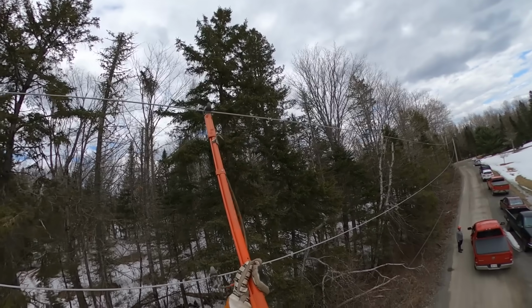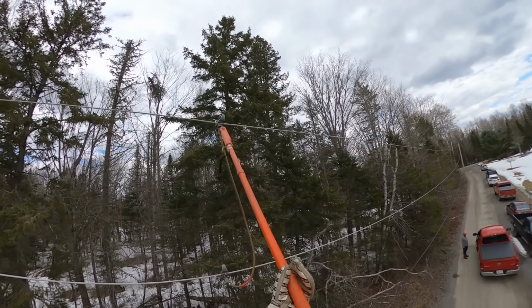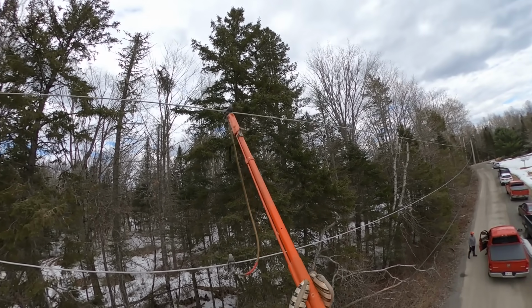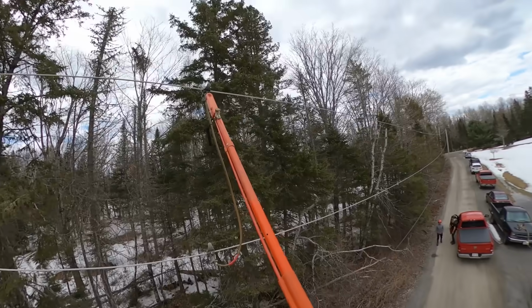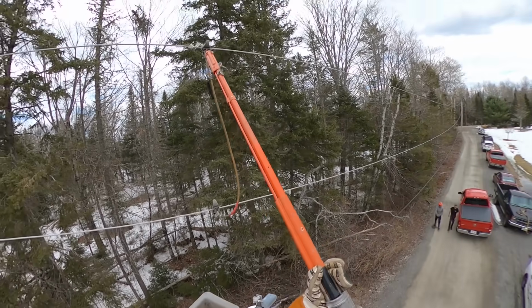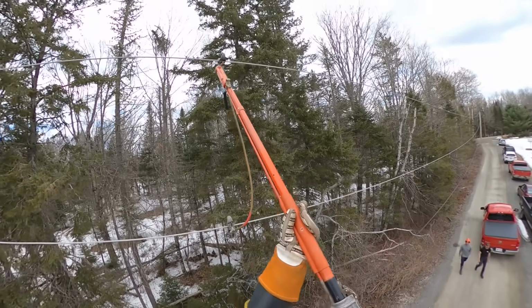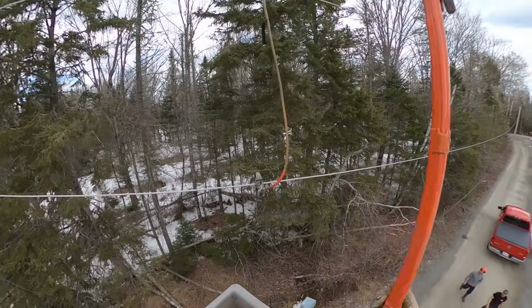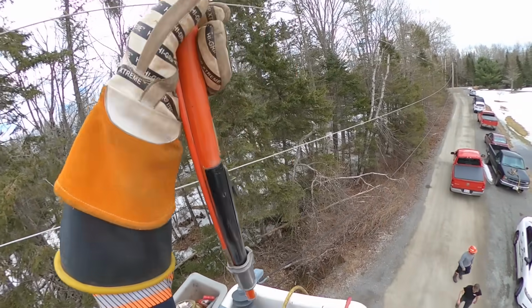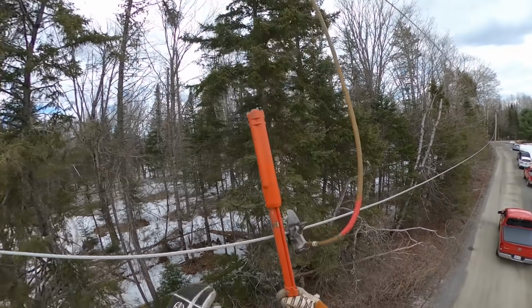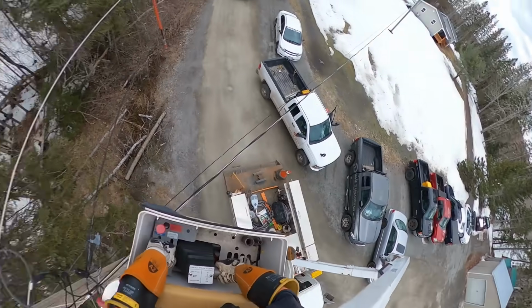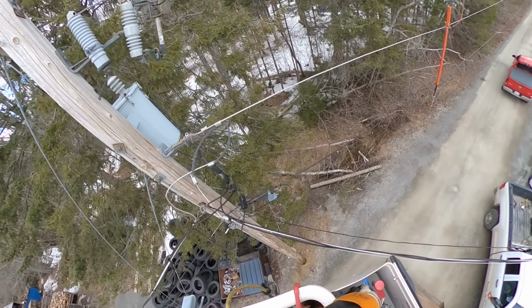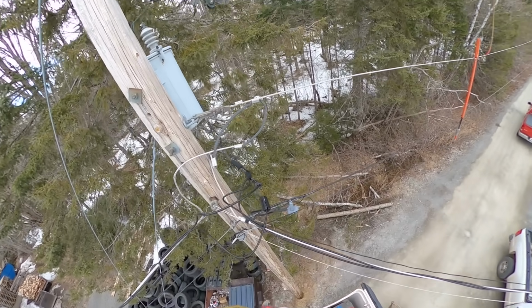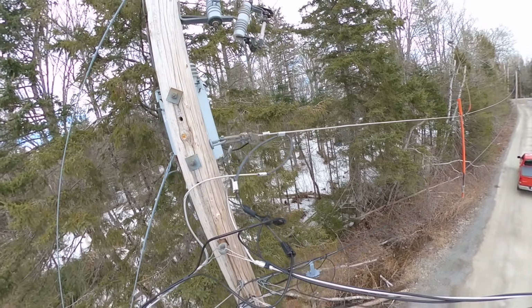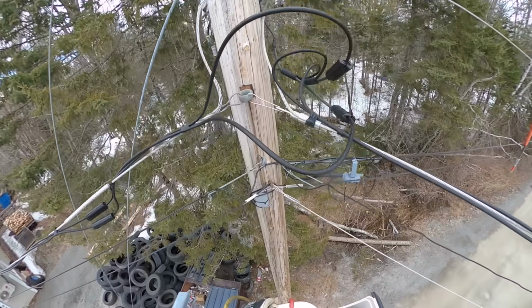It's important to slap your grounds on quickly. You don't want to tease the line. If by chance that line did become energized, once that ground is on the primary seated tightly, it's going to blow the fuse or the recloser or whatever's feeding that line. If you start teasing that, that's when you can draw some arcs and get some arc flashing going on. So I just hang my stick over there. We're not going to be touching the neutral. I wouldn't recommend hanging your stick on a neutral or phase like that if you're going to be transferring that. It's a good way to drop your stick, but we're not going to be touching the neutral.